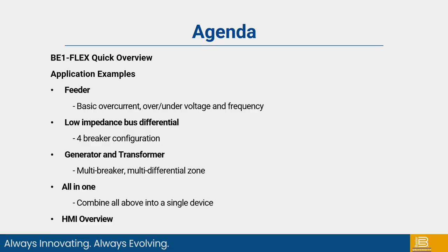So first, let's go over the agenda. First, I'll do a BE1-FLEX quick overview, and then we'll go through 4 or so application examples. The first one being a feeder application with basic overcurrent, under voltage, and frequency protection. The second example will be low impedance bus differential with a 4-breaker configuration.